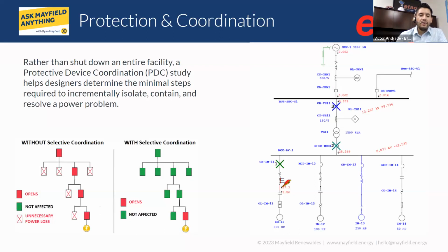Now, I want to build my system more redundant, so I want to know, in the event this protective device doesn't trip for whatever reason, right? Or if I have a fault on the line side of that device, what would be the next protective device to clear that fault? So that's number 2, and then obviously number 3 and 4. It's very unlikely that the first 2 will not trip, but I'm just giving you a quick overview of what the capability of a software would be to look at multiple different operating conditions.